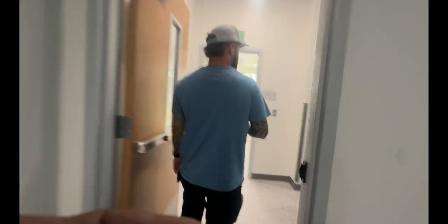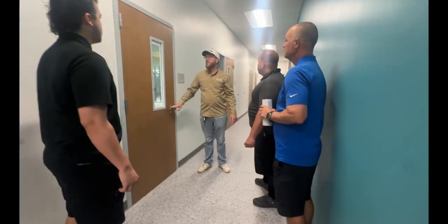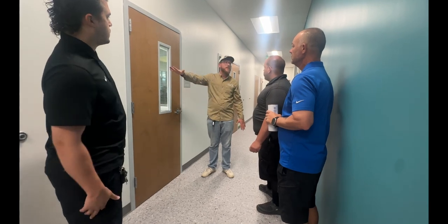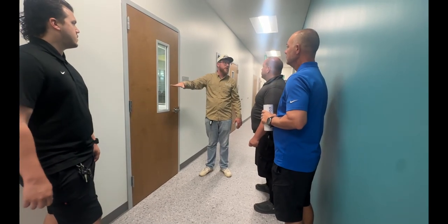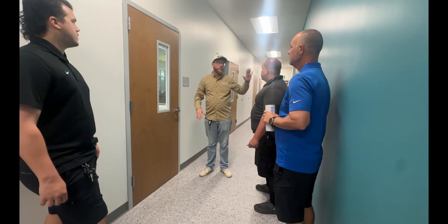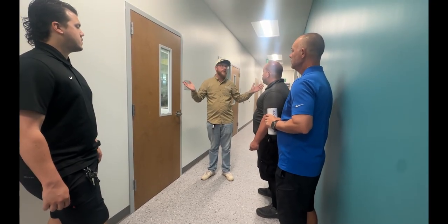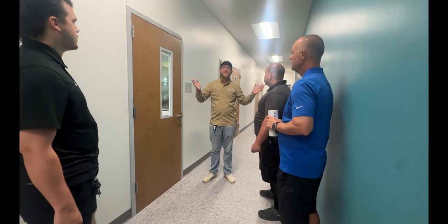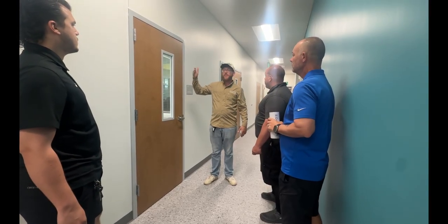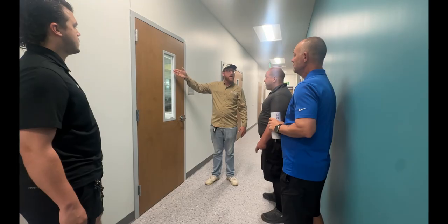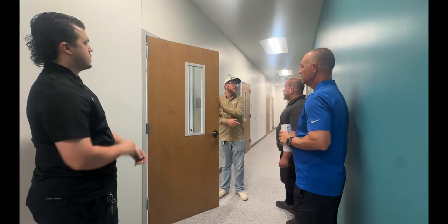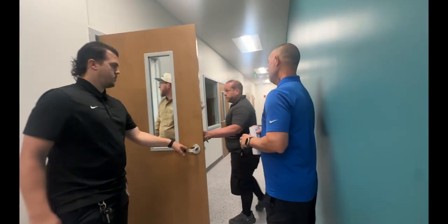All right, good deal. That's where you can disable the relays and stuff like that, so that the AC units keep running and everything. Usually I know with the county, if you do a fire drill, you choose a pull station, just the pull station itself. So you can go and disable the relays. Make sure the AC stays on and the smoke doors stay open. You don't have to worry about little kids getting closed inside of those because they slam pretty quick. There's a pull station up here by the annunciator, which we'll go to, and then you can just hit that. And I'll show you, we have some keys that you can use to reset it and everything.